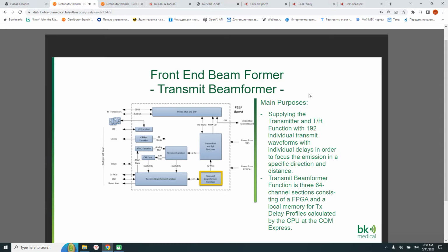Transmit beamformer function is supplying the transmitter and the transmit receive function with 192 individual transmit waveforms with individual delays in order to focus the emission in a specific direction and distance. The transmit beamformer function is built as 3 identical 64-channel sections, each consisting of an FPGA and a local memory for TX delay profiles. These profiles are calculated by the CPU on the COM Express carrier board and transferred to the local memory by using the DMA controller in the PCIe switch function on the SCP card. Apart from generating transmit profiles, the transmit beamformer function also controls the high-voltage multiplexers and handles real-time signals to and from the probe connectors in the probe mux and the SPP function.